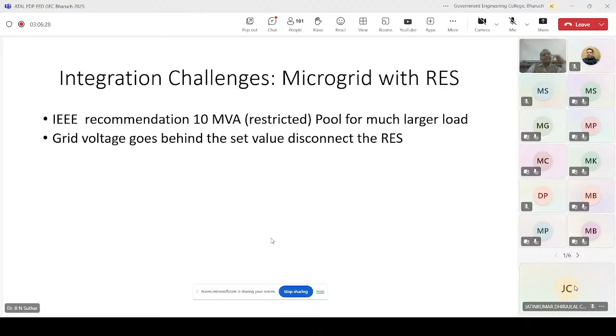If the grid voltage goes beyond the set value, disconnect the RES. Injection or withdrawal of reactive power facility should be there. It should be able to provide leading or lagging current with the grid waveforms. And it should give a fast response for frequency and voltage regulation. For that, we have different grid codes and standards. And in India, we have CEA, CERC or SERC, which decide these grid codes or standards.